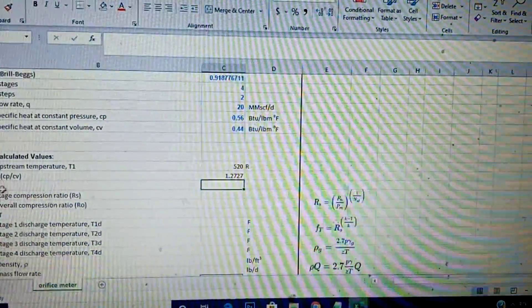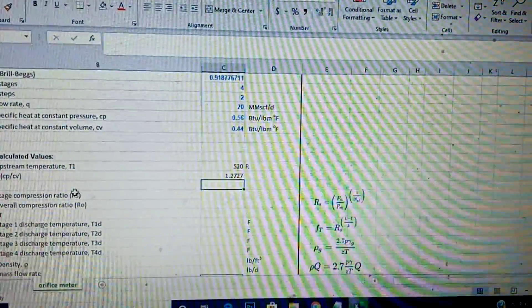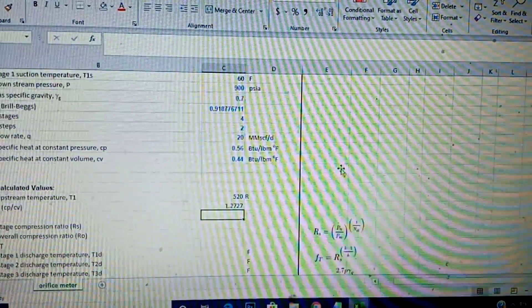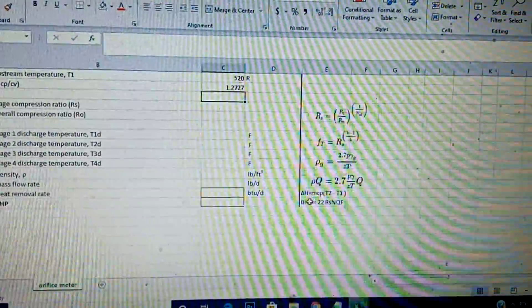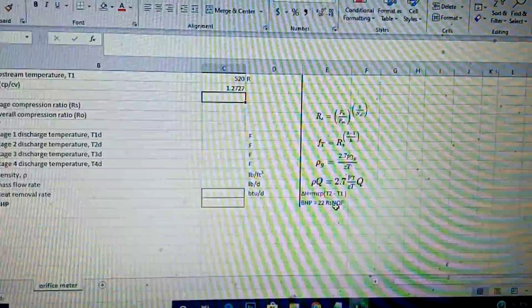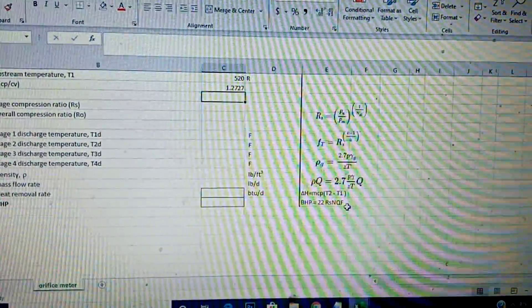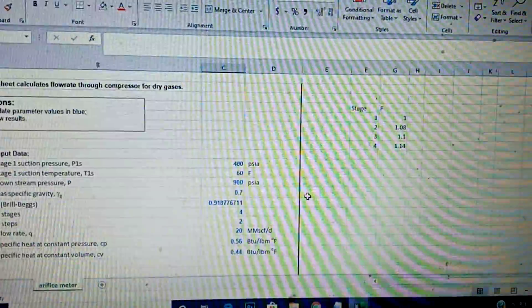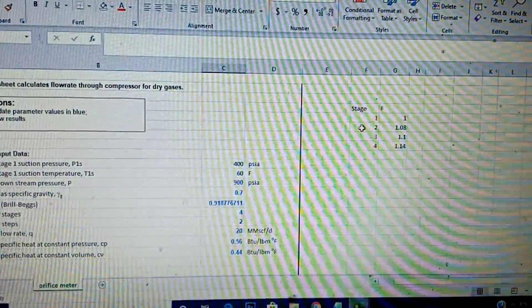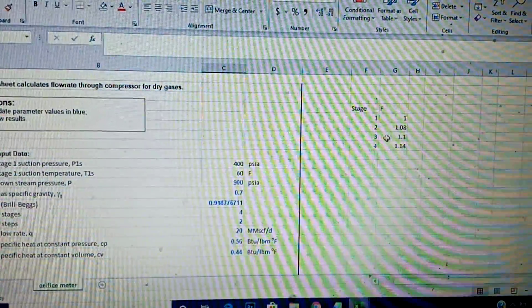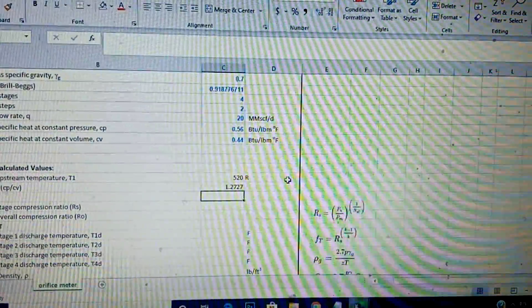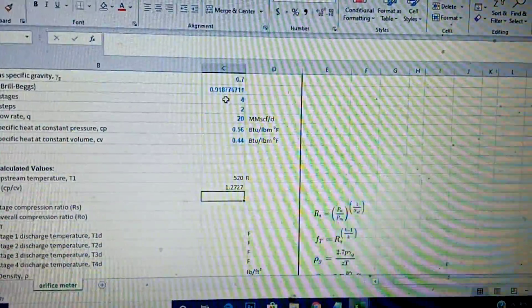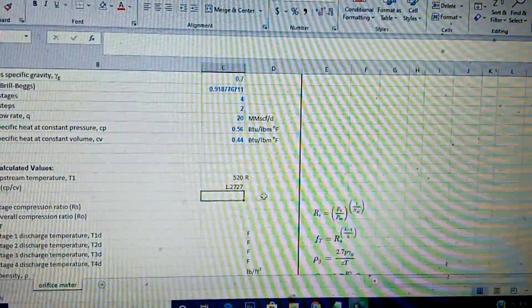Now this capital F is the factor for brake horsepower. The brake horsepower formula is 22 multiplied by the stage compression ratio, multiplied by number of stages, multiplied by flow rate, multiplied by this factor F. Per the notes, F depends on the number of stages: for one stage it's 1.0, for two stages it's different. We use LOOKUP to find the right F for the given number of stages, which returns 1.14.